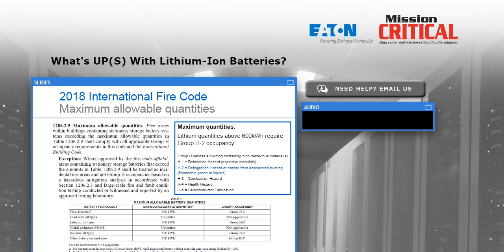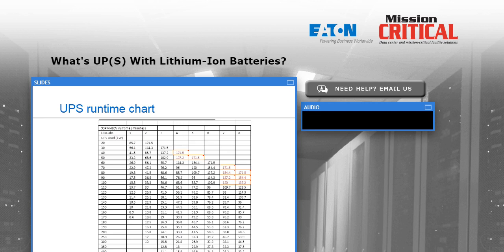Remember from the previous slide that all the lithium vendors we're seeing in the market already meet the UL requirements for deployment of this battery, both as single batteries and as large battery strings in cabinetized environments and that type of thing. So there will be some questions, answers, and uncertainty in these early years of deployment, but the good news is all of the vendors, including the UPS vendors, are making a lot of progress towards distilling these down to a reasonable set of requirements that the authorities having jurisdiction can consult quickly and say okay, this is good enough, or it's within the limits, or it isn't. We want to try to limit the confusion, obviously.